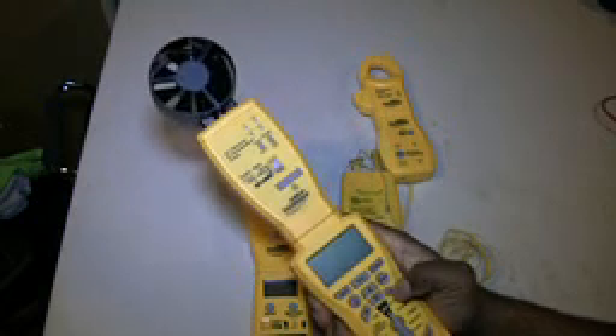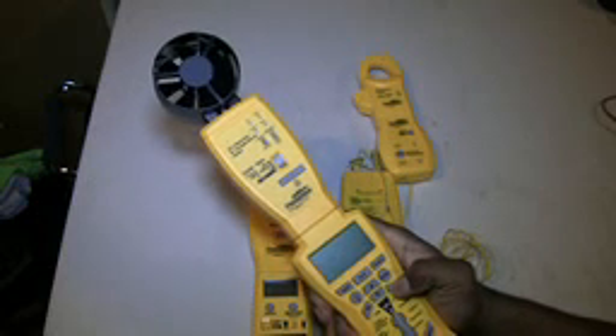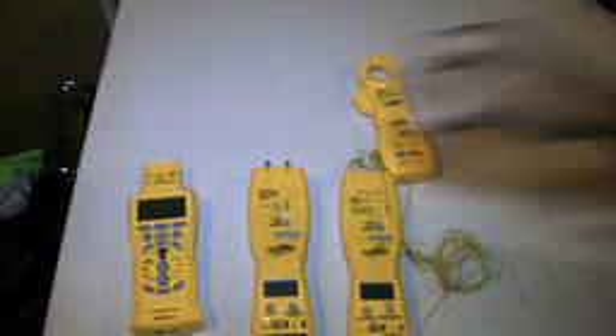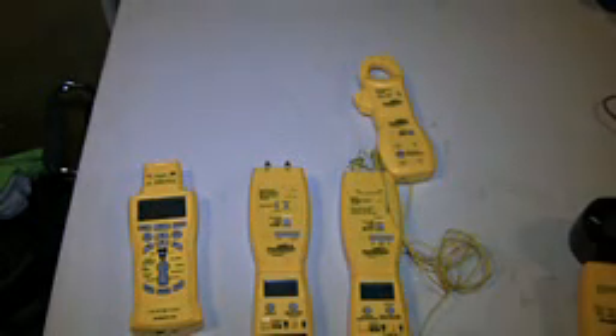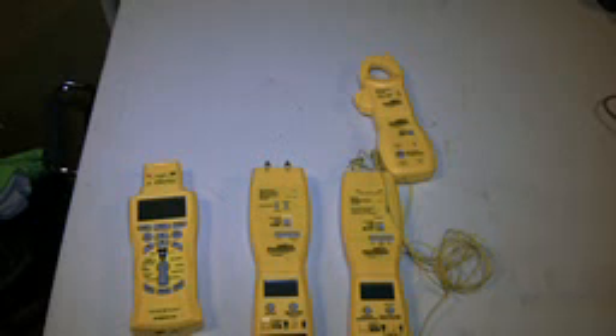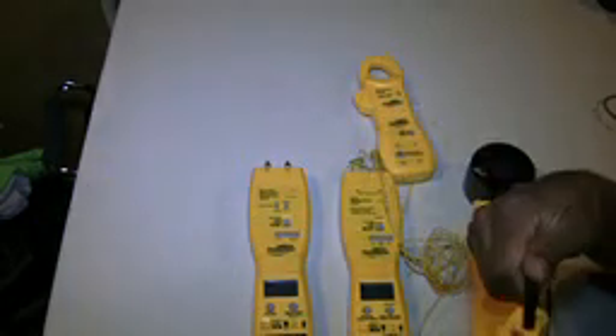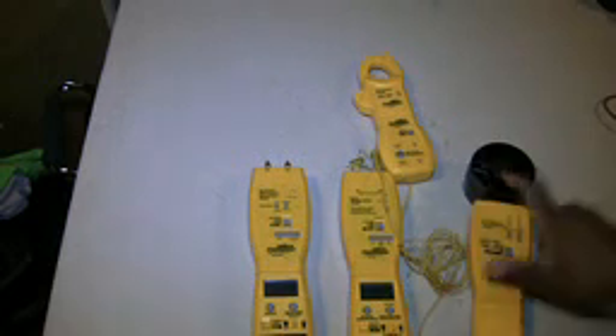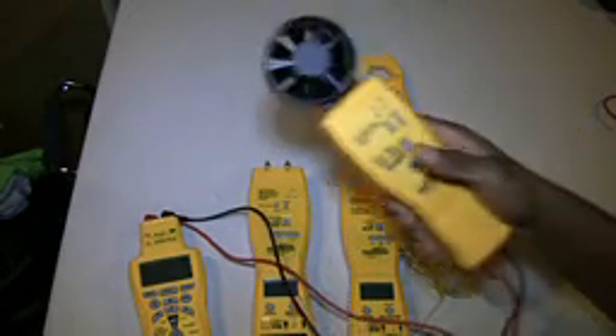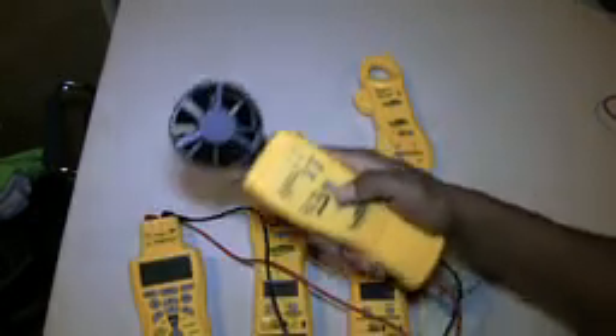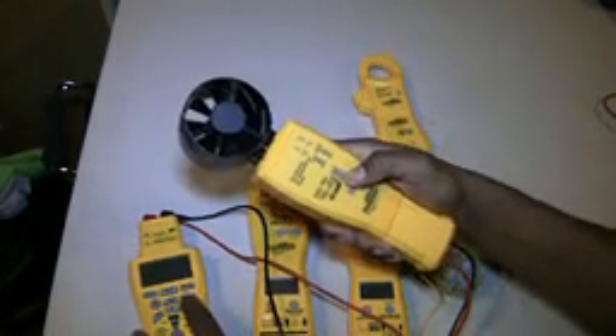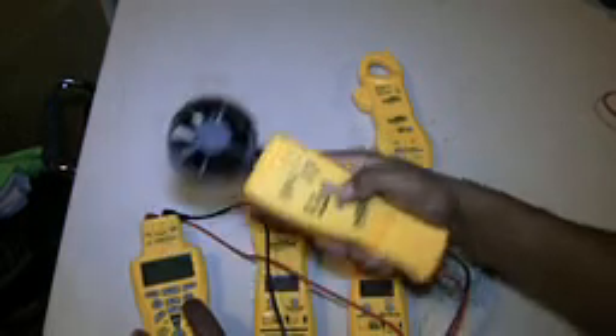With this, you have to keep hitting the arrow button to take measuring points across the register or grill, or you do a two-hand operation: lay this flat on top of the ladder, and use your other hand to go across the grill, hitting points as you go. Once you're done, you hit enter to get your total CFMs going into your return or coming out of your supply.